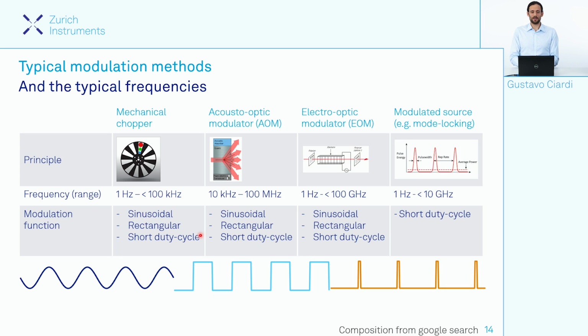Which are the most common kinds of modulators that we can find for optical experiments? Well, there are many different types, and which one to use depends a bit on the frequency range that we want to achieve. We can start with very classic mechanical choppers, where the light is mechanically blocked by a spinning wheel. The frequency range achievable by these devices is of the order of tens of kilohertz. And then, if you want to move to higher frequencies, up to tens of gigahertz, we need to resort to a more complicated device like acousto-optic modulators or electro-optic modulators. Alternatively, there is also, of course, the way of using a pulsed laser system, for example a mode-locked laser, that is naturally modulated at the repetition rate of the laser itself.